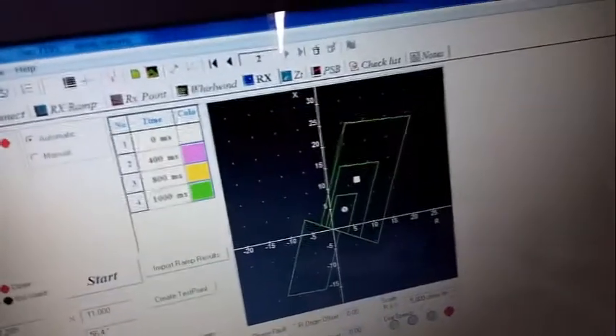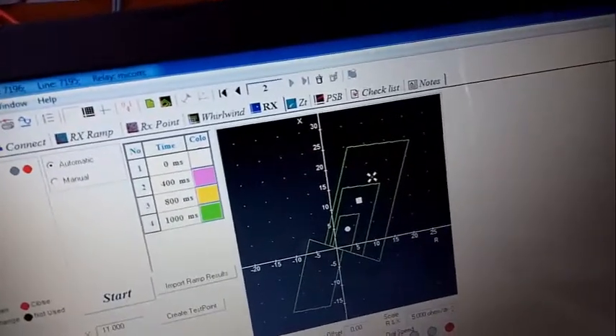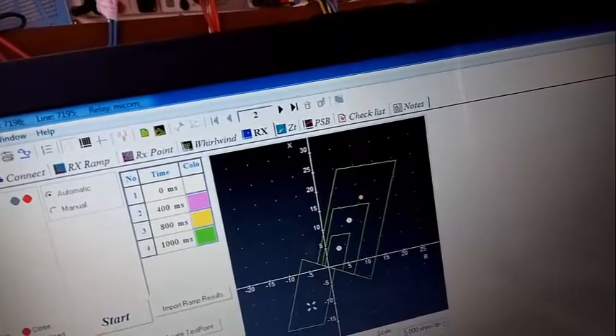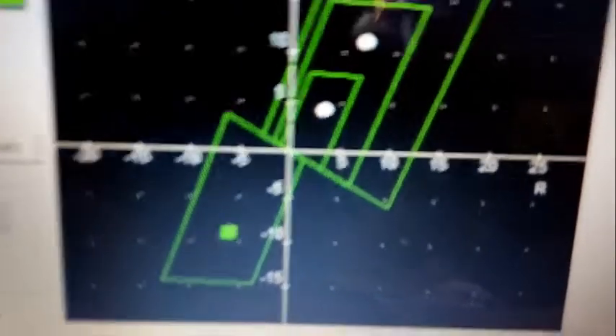The display is showing number one again because this has been considered as time zero, since we enabled the Permissive Under Reach scheme. Now we will create faults in different zones and start injection to observe results: zone one, then zone three, and then zone four. This was all about the Permissive Under Reach scheme.